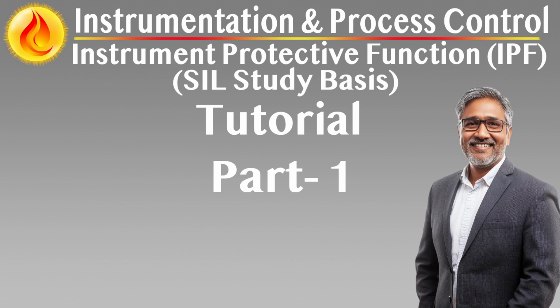In the plant, all IPF-related devices must carry distinct tagging, both in the loop diagrams and physical nameplates. Visual differentiation, such as red-on-black tags or distinct enclosure coloring, helps prevent unintentional modification or removal. Instrument cabinets and junction boxes associated with IPFs must be similarly marked and secured.